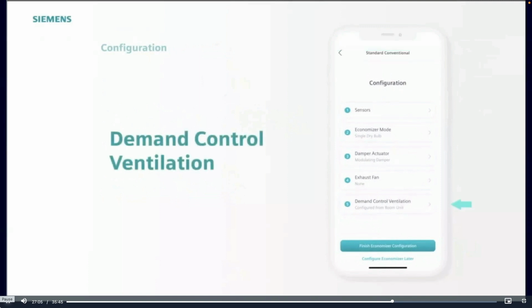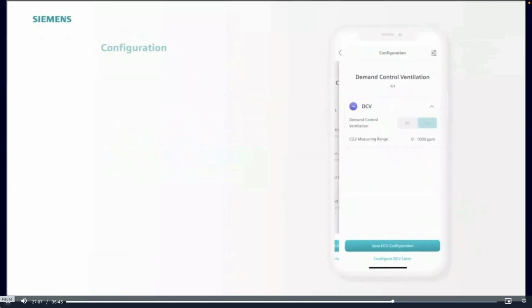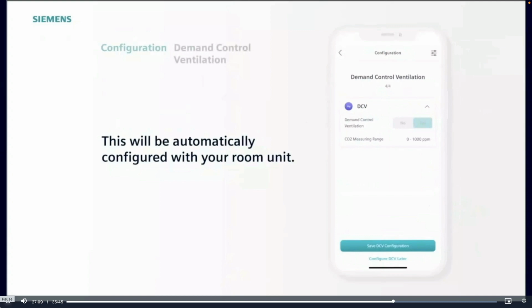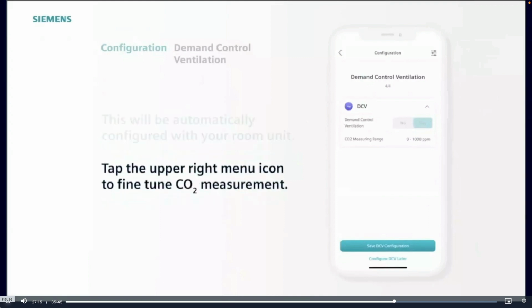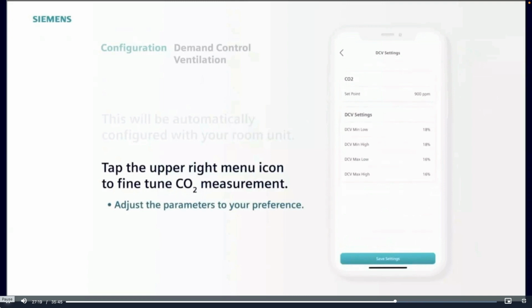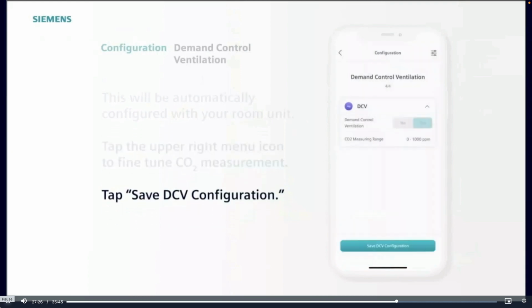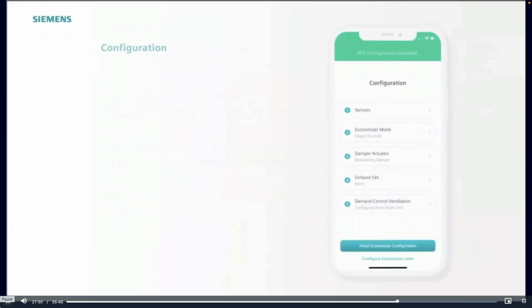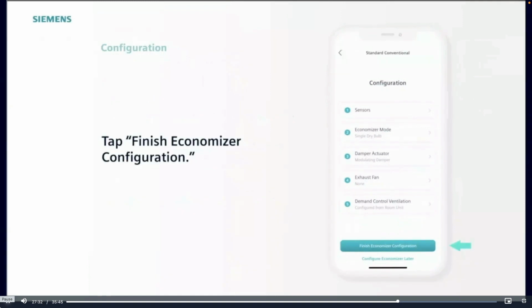Then select Demand Control Ventilation to optimize your indoor air quality. This will automatically be configured with the QMX3, P74, and/or the P70 room unit sensors. To fine-tune the carbon dioxide measurement in parts per million, tap the right menu icon. Here, you can adjust your set point in DCV min-max settings. We'll leave it at the defaults for this example and tap Save Settings. Then tap Save DCV Configuration. And finish up the configuration by tapping Finish Economizer Configuration.